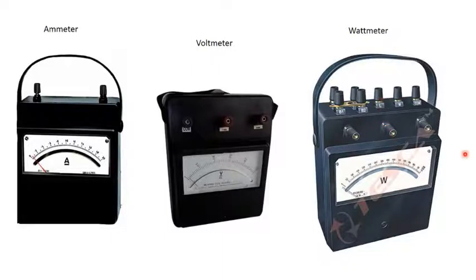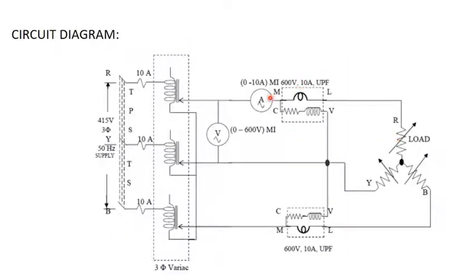M will be connected to the main and L will be connected to the load. This is the circuit diagram. This is the TPST and this is your supply, and this 10 amps represents your fuse, and this is your auto transformer, or what you call a 3-phase variac. By varying this variac, you can give the rated voltage to the circuit. You can see here the voltmeter is connected in parallel and the ammeter is connected in series. This is your 2 wattmeter.